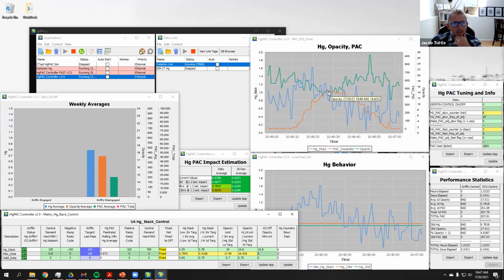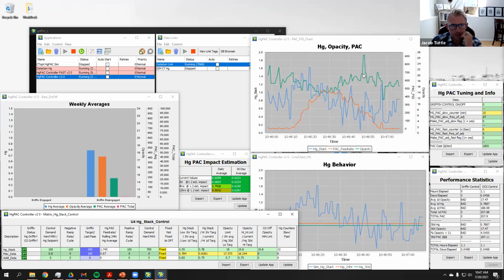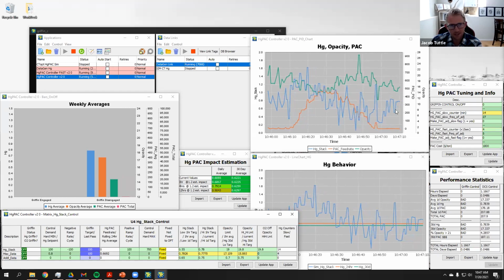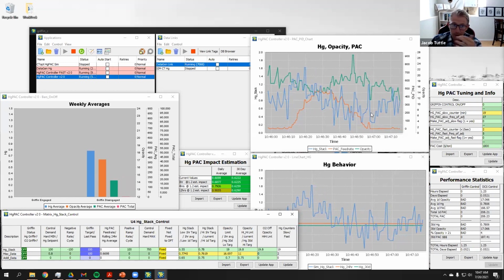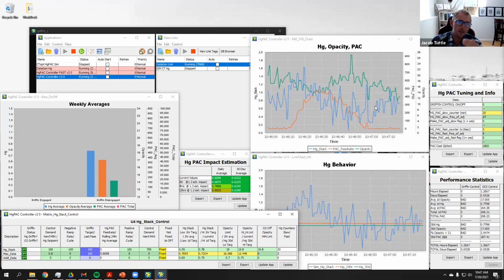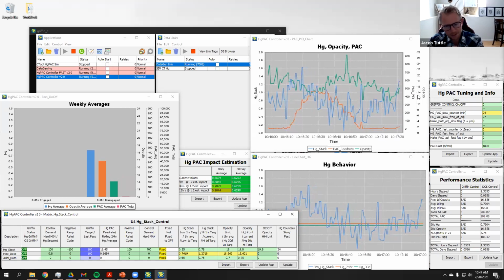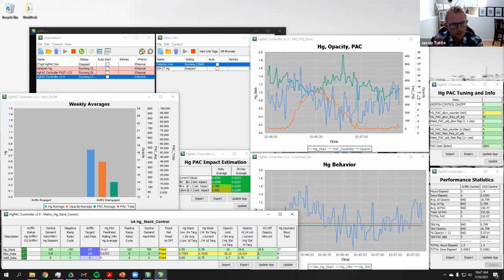See that right here, PAC increased and opacity started to increase on average in general. Now PAC has come out of the system in DCS control, and slowly opacity is kind of rolling out. But we also see mercury will start to trend up. But really what's key in this application, as mentioned, is the time frames that each of these constituents are concerned with.